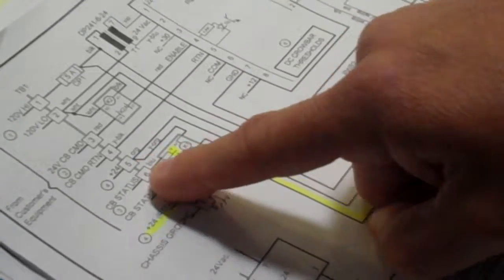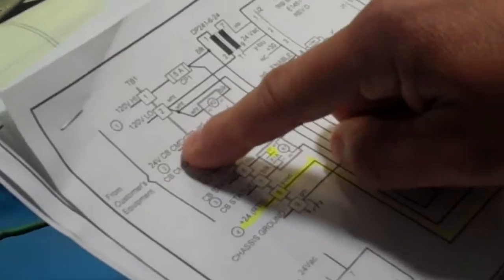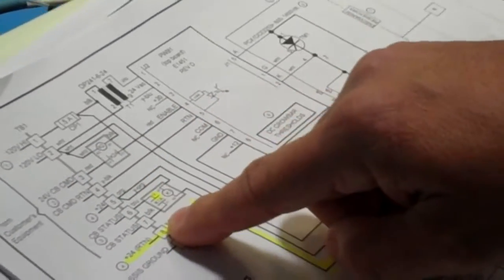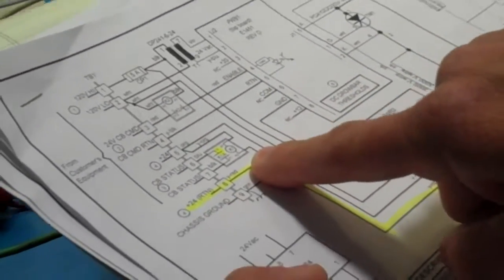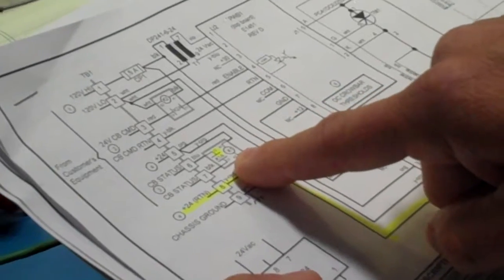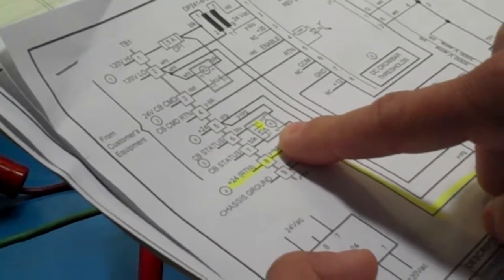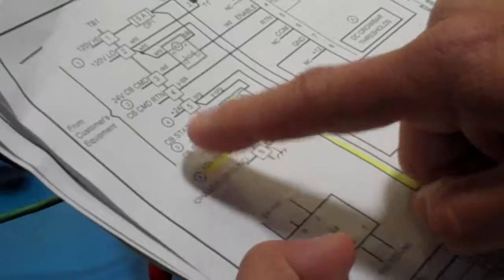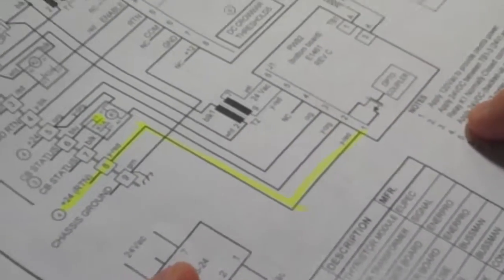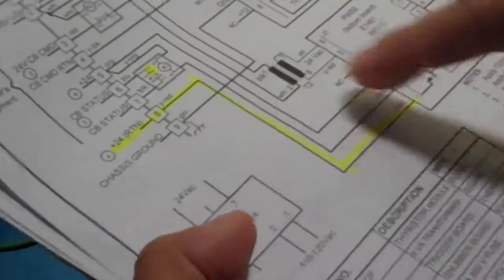Here we have the 24 volts DC with its associated return, which could be the same 24 volts. However, we wanted to make sure that this was independent, because it's going to provide a status of whether the unit is crowbarred. According to note 3 and the requested logic, that relay is normally closed and it will open when the unit crowbars.